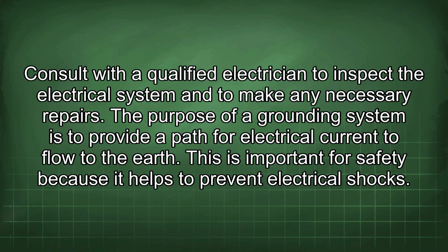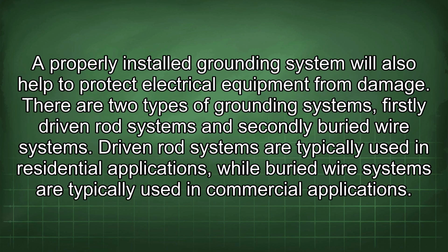The purpose of a grounding system is to provide a path for electrical current to flow to the earth. This is important for safety because it helps to prevent electrical shocks. A properly installed grounding system will also help to protect electrical equipment from damage. There are 2 types of grounding systems: firstly, driven rod systems, and secondly, buried wire systems. Driven rod systems are typically used in residential applications, while buried wire systems are typically used in commercial applications.